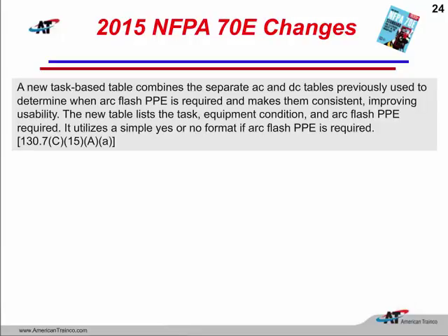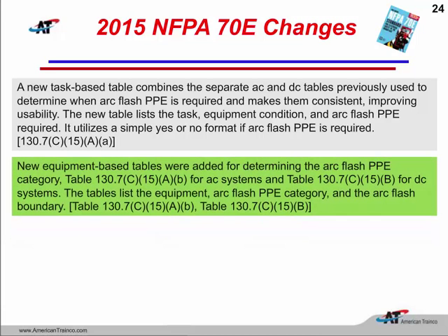Okay. The tables. So as we decide which method we're going to use to generate our label or keep our workers safe, if we're going to use the table method, which is now going to be called the Arc Flash PPE Category method, then these have been revised. They have some separate tables for AC and DC, and they're going to list the task out. We've got to make a determination of the condition of the equipment. So we've got to answer some questions before we're able to use these tables. There's going to be a yes and no format to do this, and the table is going to determine, are we going to need Arc Flash PPE or are we not going to need that? So that's going to be very important.